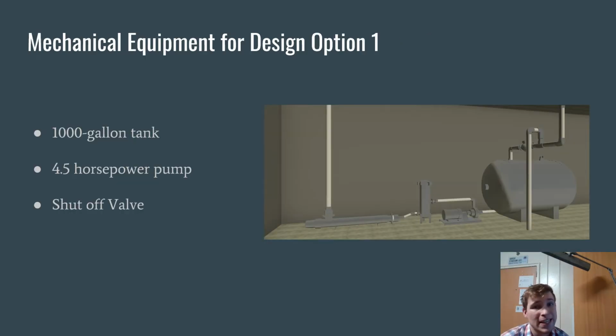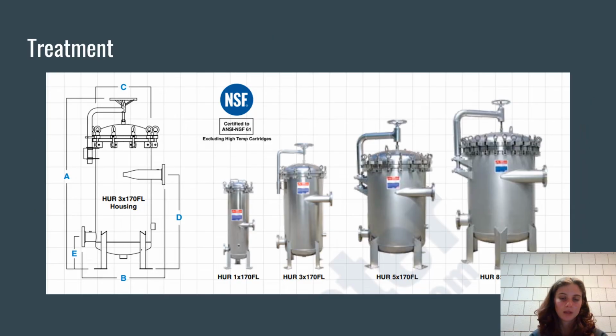To the right is a CAD model of the mechanical room. As you can see, the condensate enters to the right. We have a shutoff valve at this point so the system can be shut down during the winter months to prevent freezing. The condensate then moves through the rest of the system and is transported out of the mechanical room. We specified the filter based on the flow rate, the pressure loss, as well as the amount of TSS, and these were the options. The one chosen is the one on the far left.